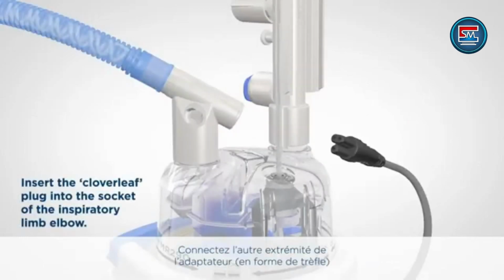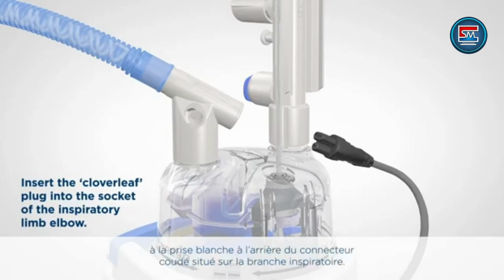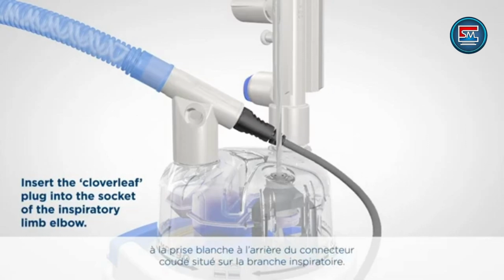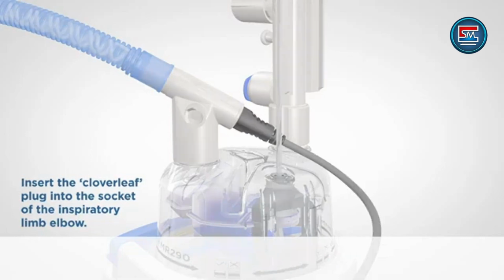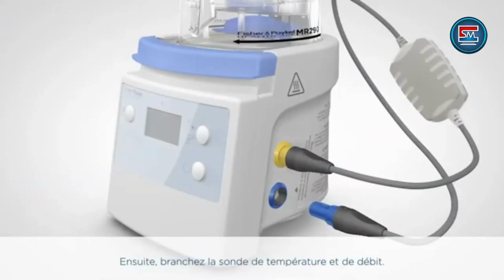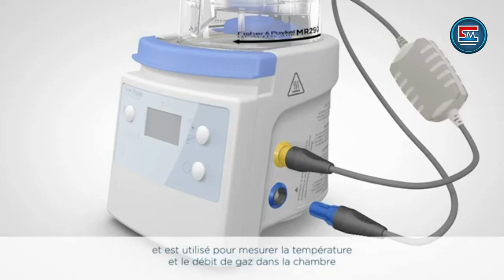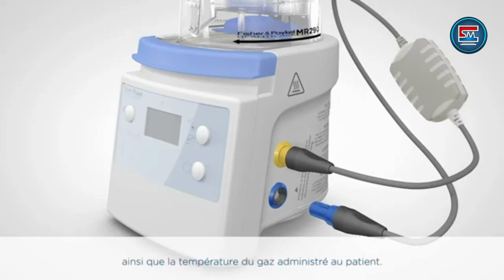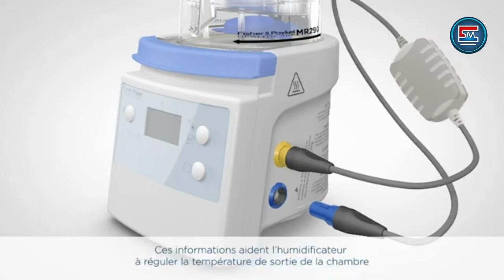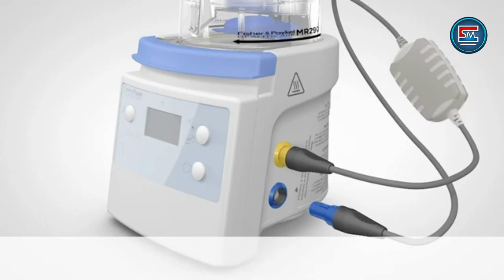Connect the other end of the adapter, shaped like a cloverleaf, to the white socket at the back of the elbow connector on the inspiratory limb. Be careful to line the plug and socket up to avoid damage to the breathing circuit or adapter. Next, let's connect the temperature and flow probe. This adapter has a blue plug and is used to measure the temperature and flow of gas at the chamber and temperature of gas delivered to the patient. This information helps the humidifier control the chamber output temperature and the breathing circuit temperature to ensure optimal humidity delivery.